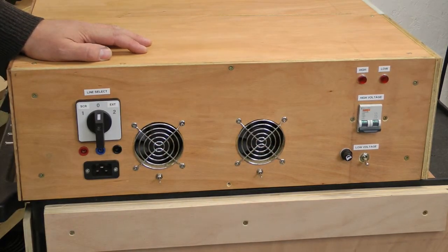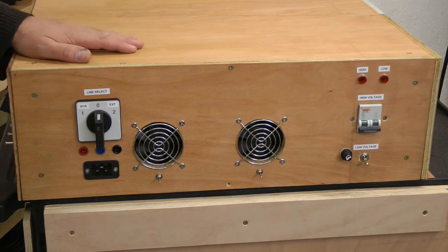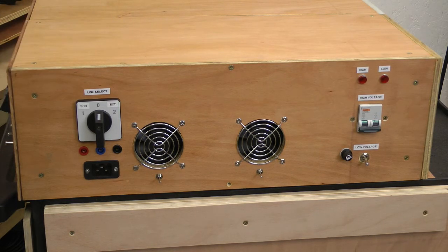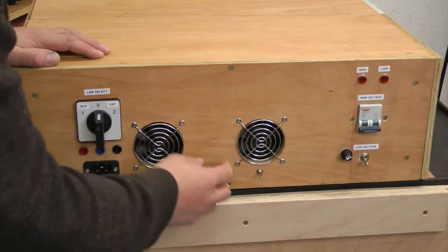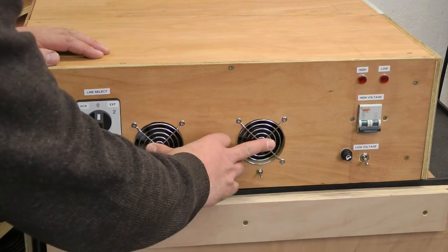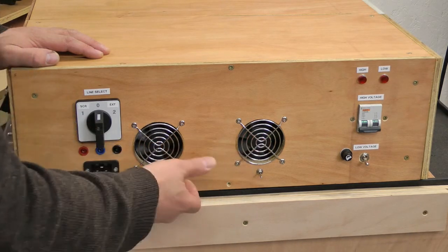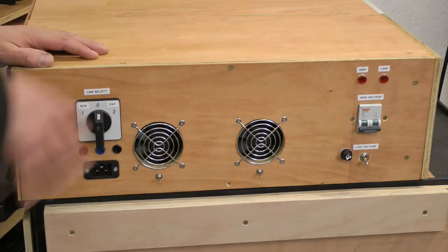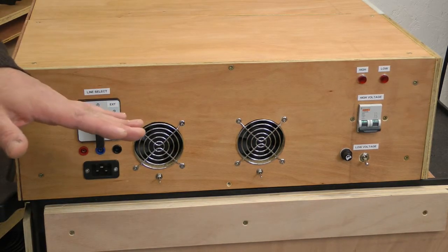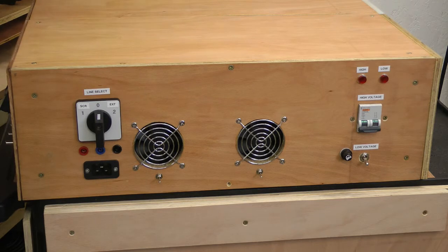Behind here then you have an SCR, so power control internally is accomplished by an SCR. The SCR sits behind here, the panel, and then the low voltage power supplies here. Two fans drawing in, and they can both be switched. They go behind the transformers, and they provide laminar airflow across the power supply and out through the large vent on this side. Particularly useful when you're working for sustained periods of time or at relatively high powers.